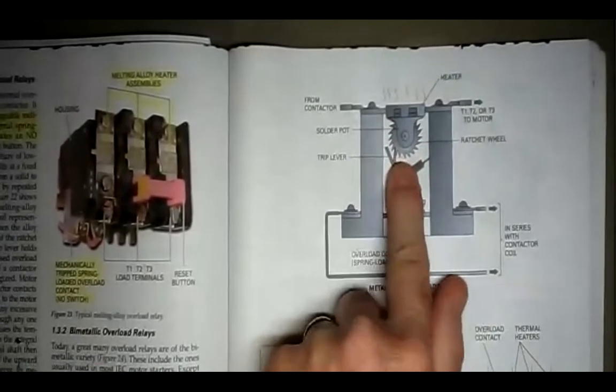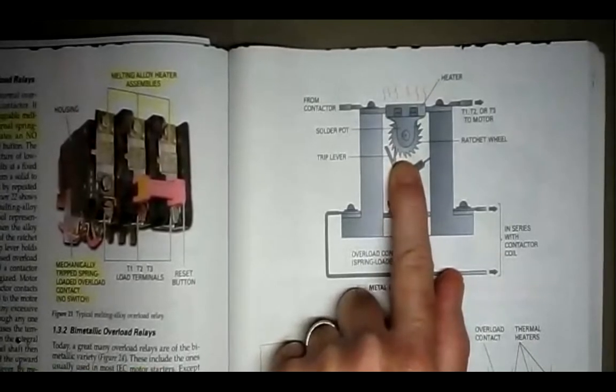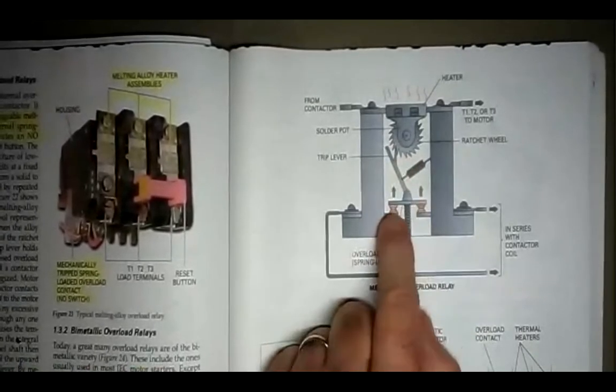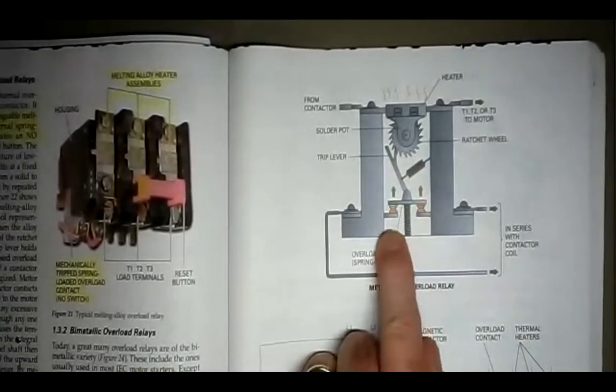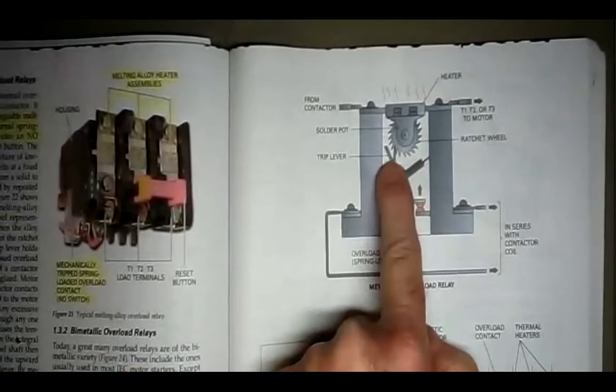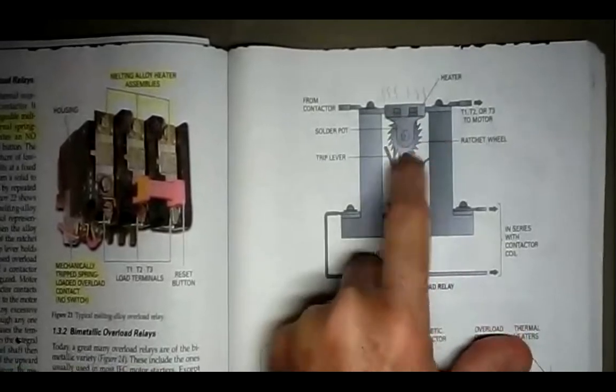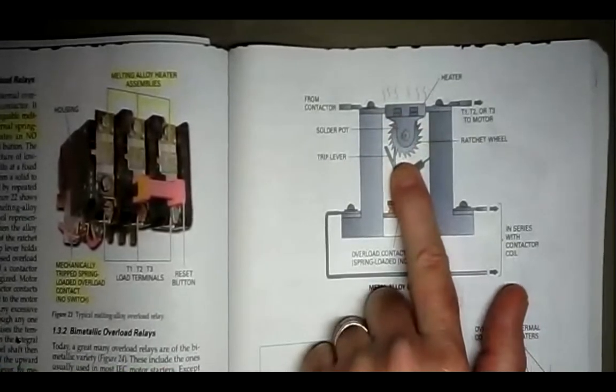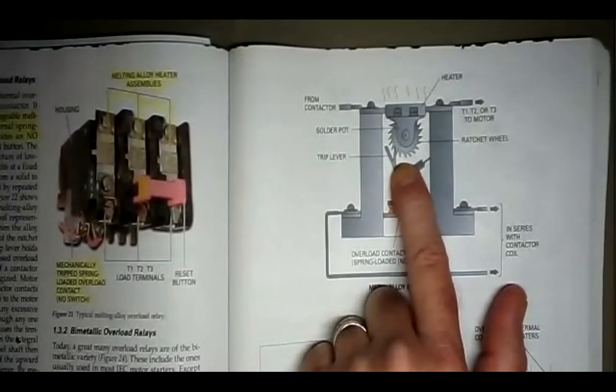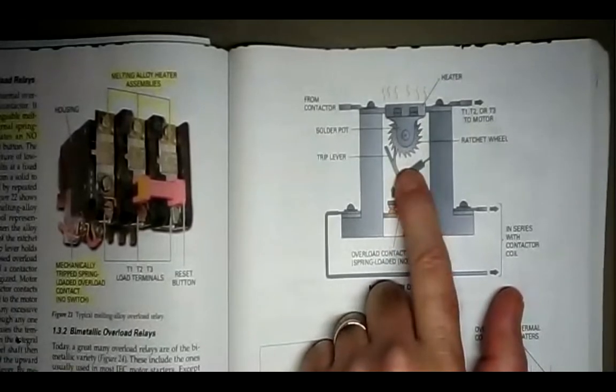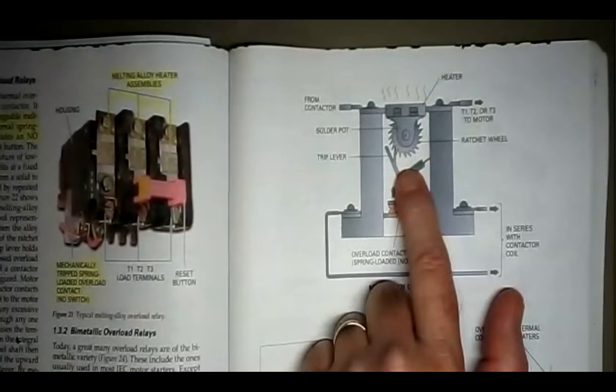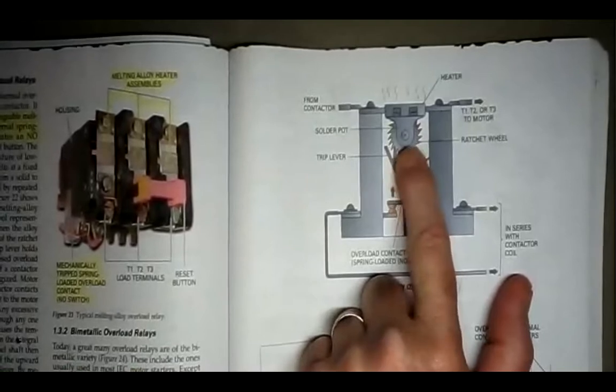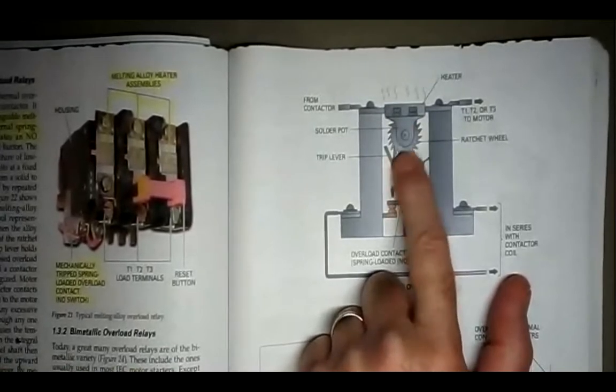There's solder inside this tube that's holding the axle for the ratcheting wheel. This is a spring-held set of contacts, and they're held by that ratcheting wheel. Now, when the solder is hard and cold, the wheel will not turn. But if it gets above 15% of the running current of the motor, if it's a 1.15 duty cycle, and we get above that, if we get to 11.5 amps or 12 amps, the solder inside of this tube is going to melt, and when it does, it's liquefied.